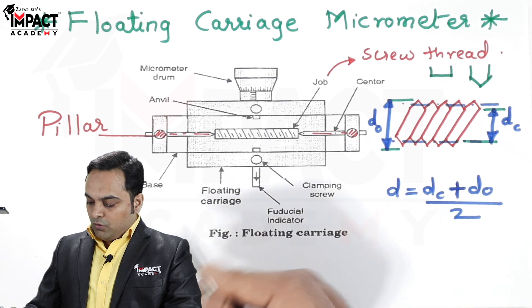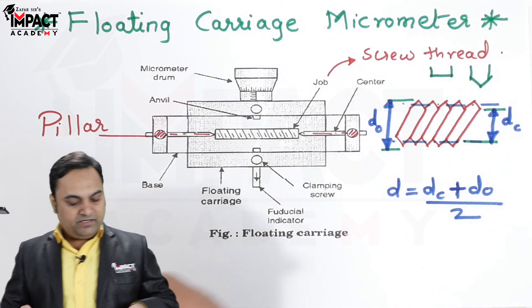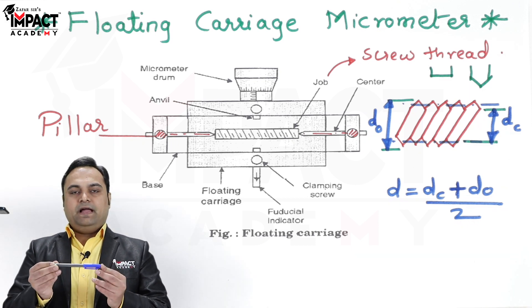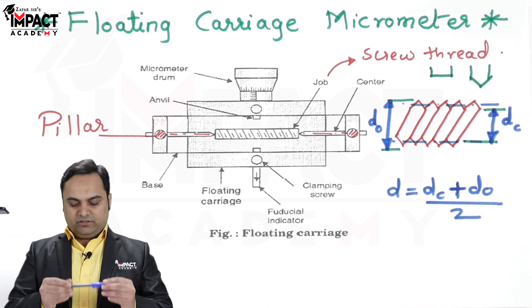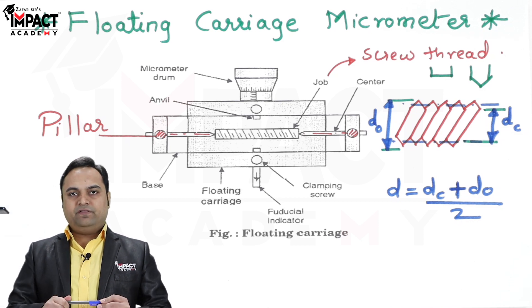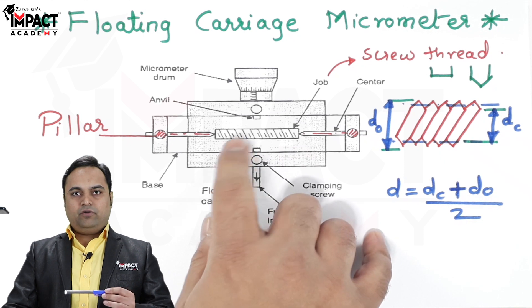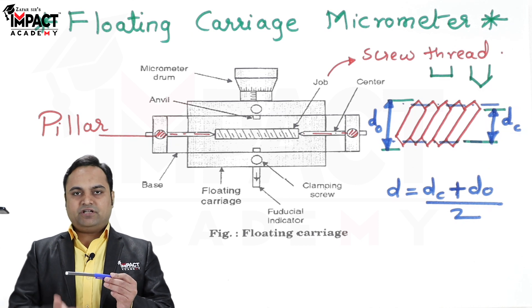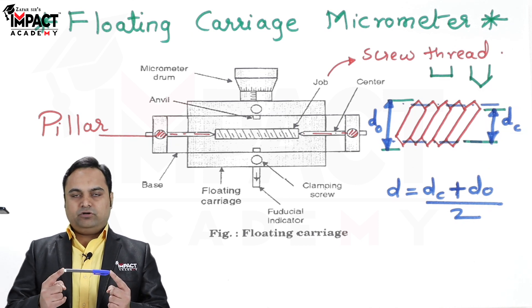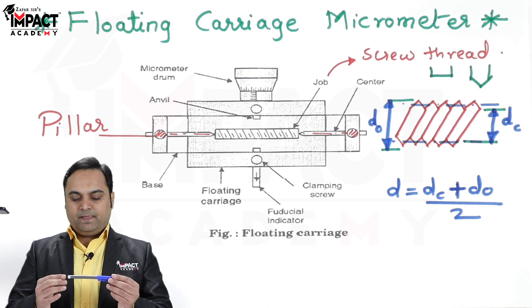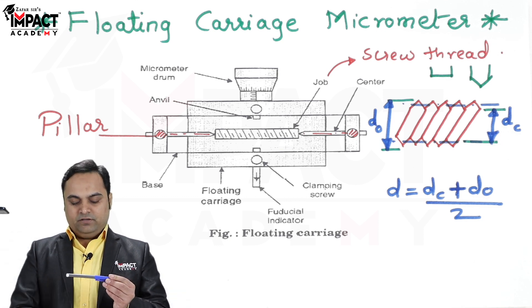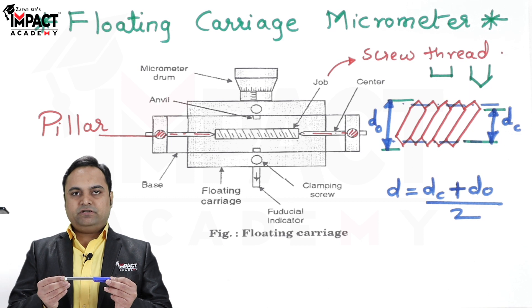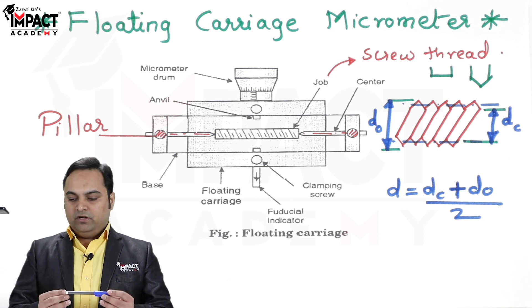Now, why is it called a floating carriage micrometer? The reason is that the screw thread is held between two centers and is not in contact with the ground or the base of the machine. Because it is held between the centers, it is at a distance away from the base — it is not lying on the table. It is held in a floating manner, and that is why it is called the floating carriage micrometer.